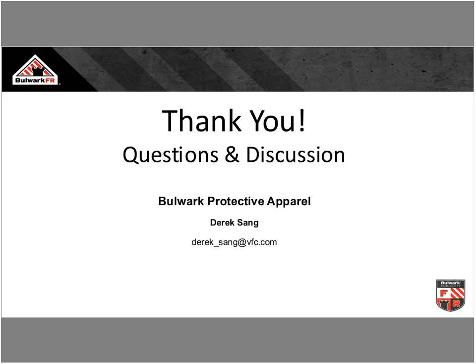DITA has a question. She asks: I often see that although there is an arc flash label on the electrical panel, my contractors generally use an infrared camera and in some circumstances don't even have to open the panel. Do we still need to enforce the FR clothing?